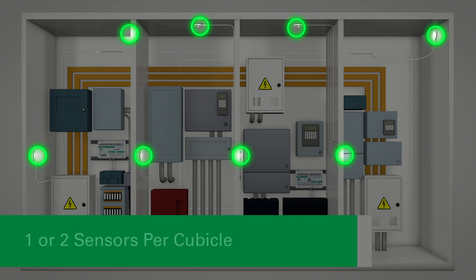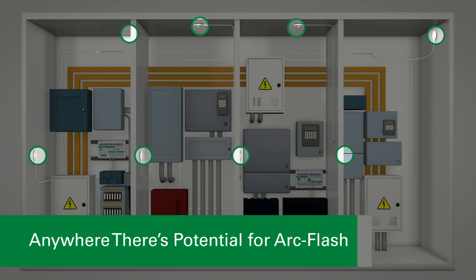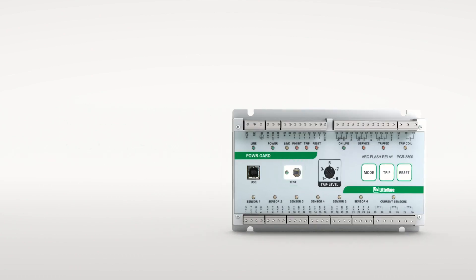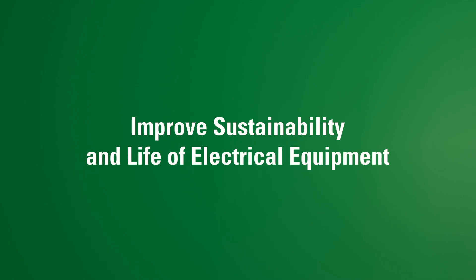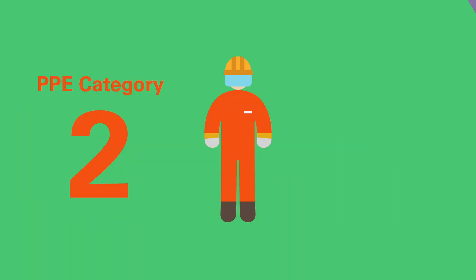Littelfuse recommends mounting one or two sensors per cubicle to cover all horizontal and vertical bus bars, breaker compartments, and anywhere there is potential for an ArcFlash. Littelfuse ArcFlash relays have backup trip paths so if one fails, the other is still protecting. ArcFlash relays improve sustainability and life of electrical equipment, and can also help lower the PPE category of protected equipment.